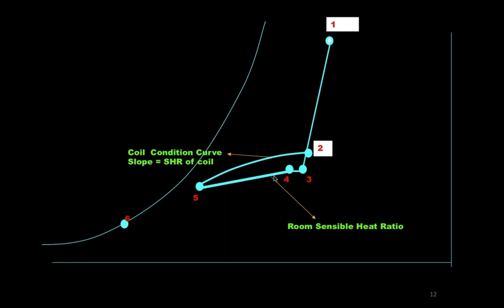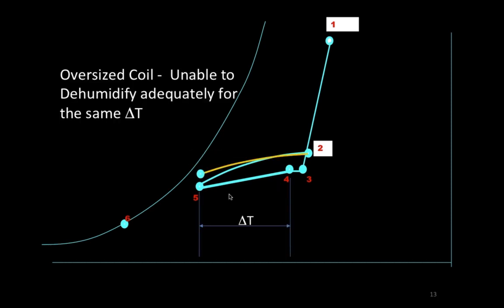If only we could replicate this at all times in the cooling coil operation in an air handling unit. Unfortunately, it doesn't happen. The coil is oversized. We try to maintain the off coil condition, say in a VAV system. I'm taking the example of a variable air volume system. We try to keep the off coil condition, say at this point 5, state point 5, because the chill water flow has been modulated or throttled.